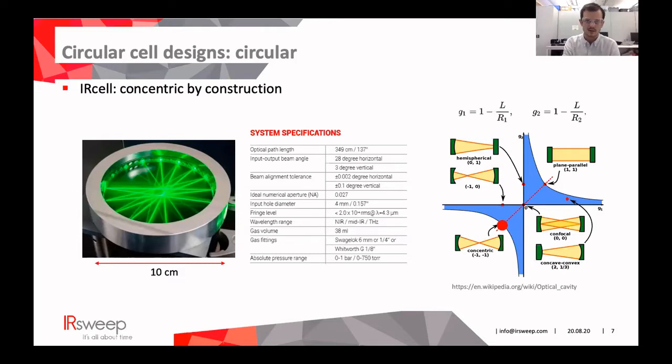This is also one of the main reasons I think the cell was historically not used so much before an absorption mask was introduced. And this is what you see here on the picture to the left. It's an IR absorbing mask placed in front of the mirror that only leaves those spaces open which are intended for beam reflection. With that, you could suppress the fringing sufficiently to make the cell usable. And this is then what we offered as the first version IR cell.